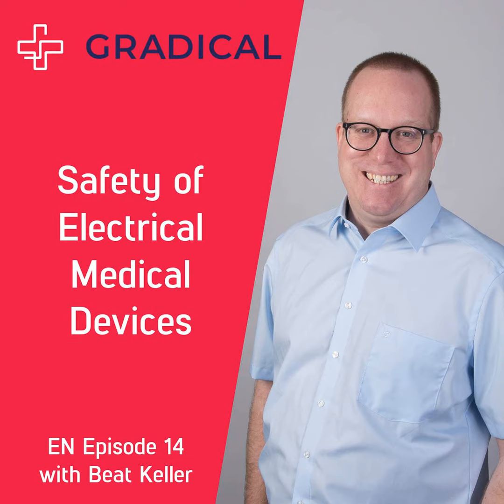So the main electrical safety norm for medical devices is the IEC 60601-1, the general standard for this kind of product. The 60601-1 family has about 80 standards in total. We have collateral and particular standards, which care about EMC, alarm systems, usability, home care, or emergency care. And then there are a huge number of standards specifically for one kind of product, such as for an MRI system or a ventilator. For ventilators specifically, there is one for intensive care, one for emergency care, and so on. So there's a huge bandwidth of standards which take care of the safety and performance of this kind of devices.